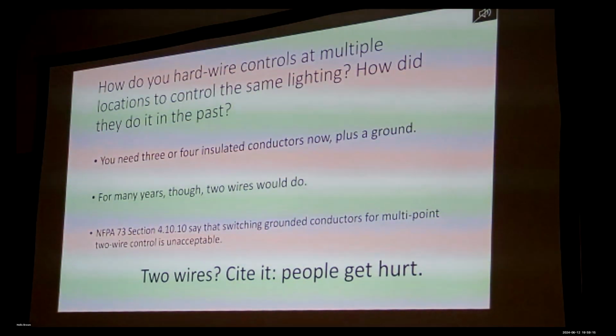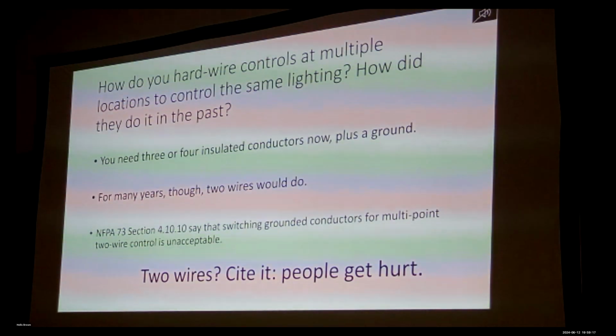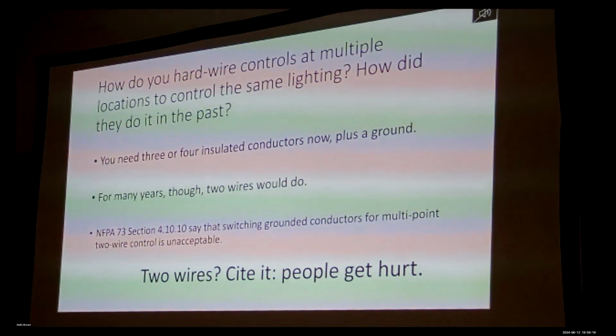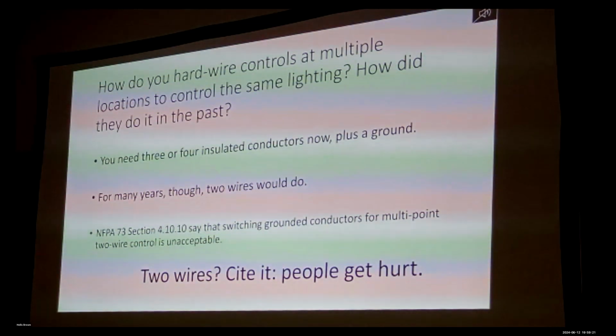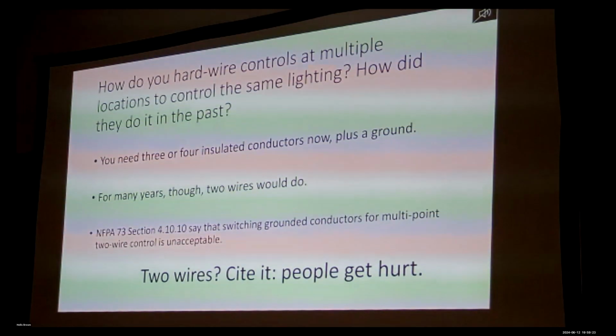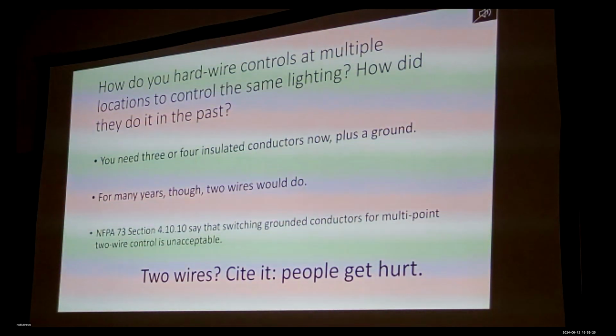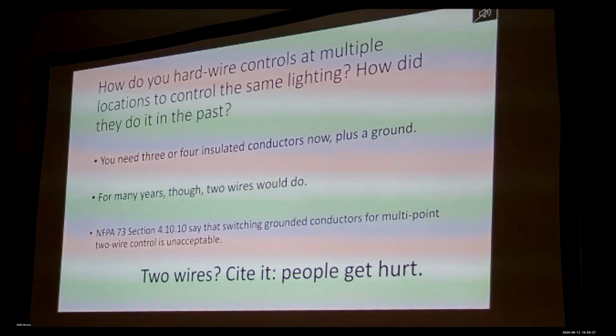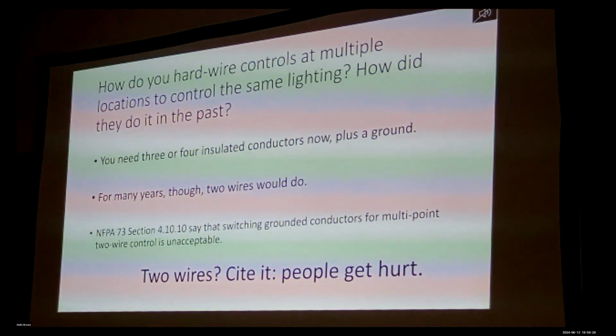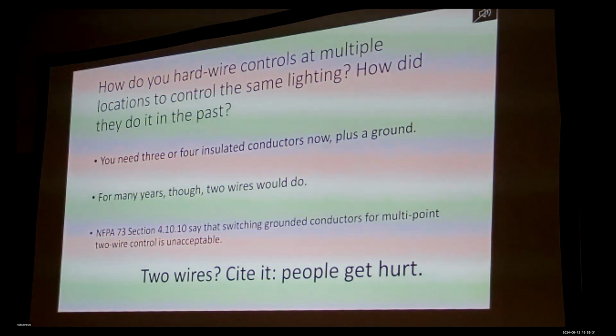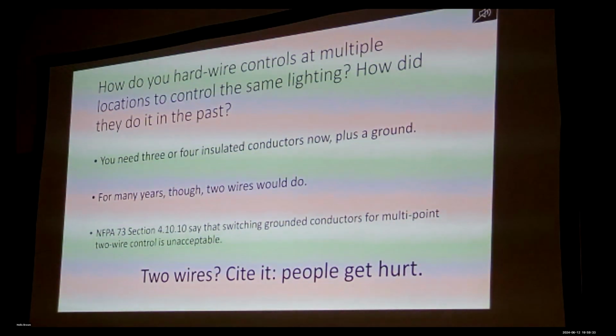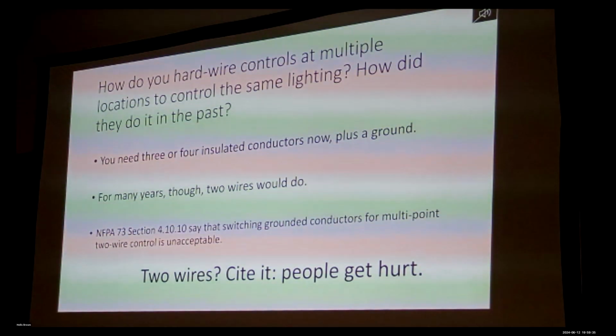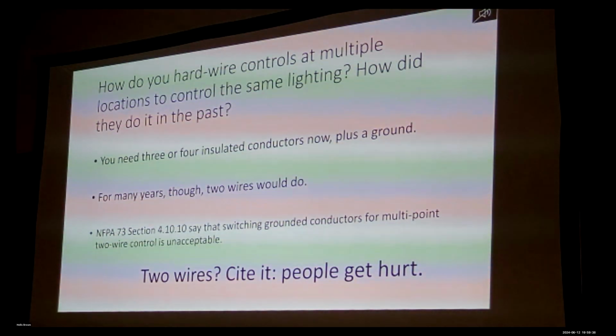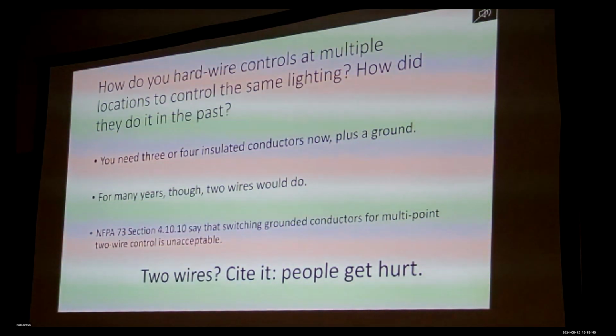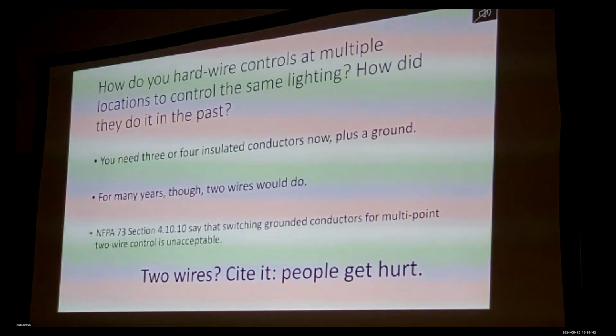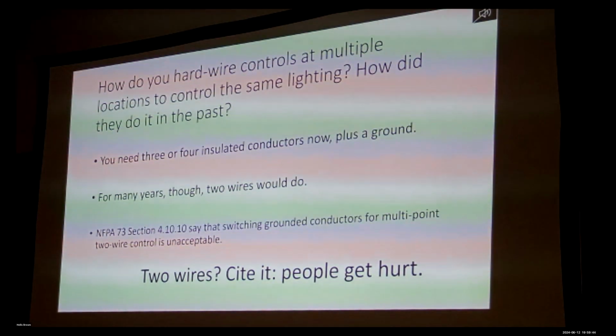Used to be, you could have two 3-way switches, and one could be up, one could be down, and it could mean the light is off because there's no power to it. Light is off because both the black and white wires are energized, or the light is on because the black wire is energized and the white is returned, or the white is energized and the black is returned.